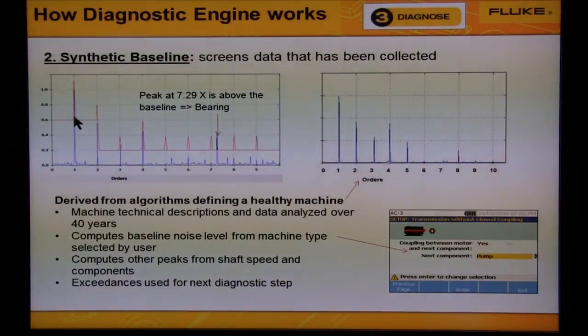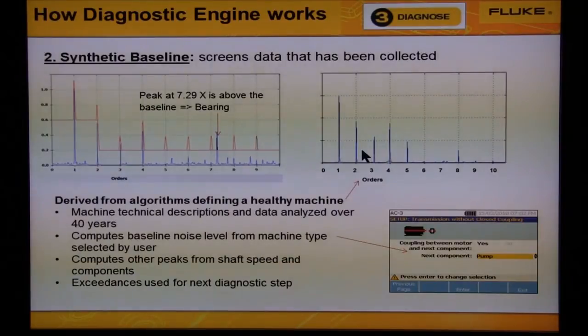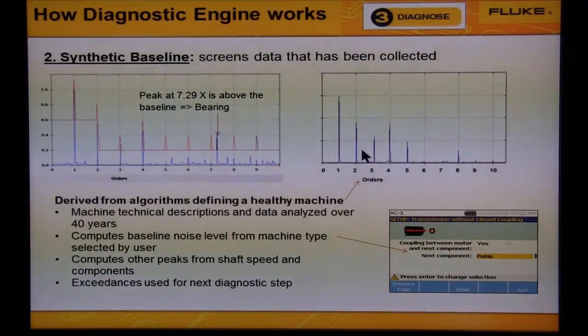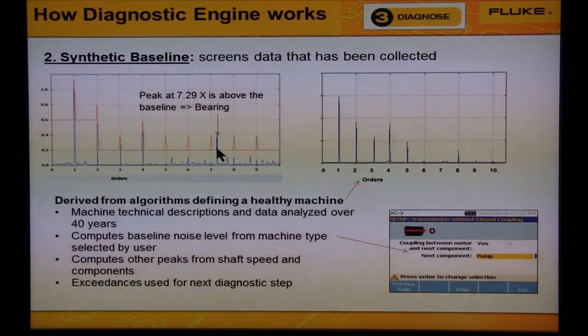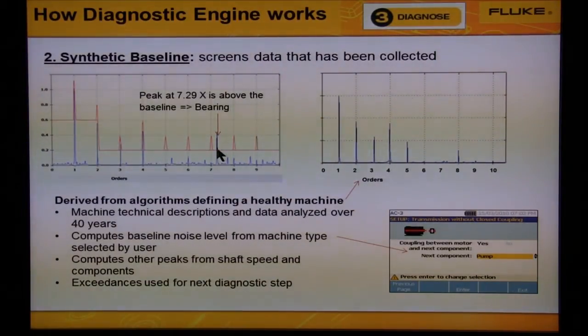We're also going to have increases at the harmonics of the shaft vibration. The graph on the right shows the data from a typical healthy machine, and notice that those peaks would all fit underneath the baseline on the left. You will notice that on the graph on the left there is a peak that exceeds the baseline — this is an anomaly that we need to find a fault or reason for, which we'll do in the next step.